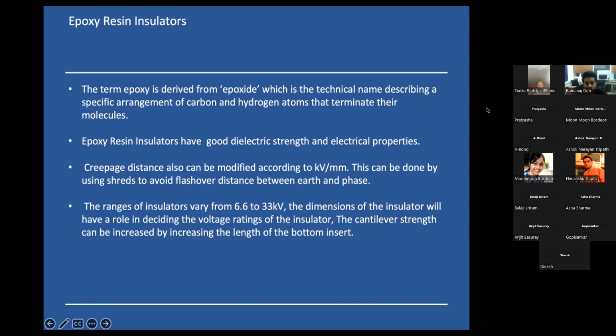The creepage distance in these insulators is easily modifiable. This can be done with the help of sheds. Sheds are used because you have to avoid flashover distance between earth and phase. Flashover is a very common problem, so this has to be addressed in the manufacturing phase itself. The insulators we manufacture range from 6.6 kV to 33 kV. When it comes to the voltage rating, the dimension of the insulator plays a key role. Without understanding the dimension, we cannot decide the voltage rating of the insulator.